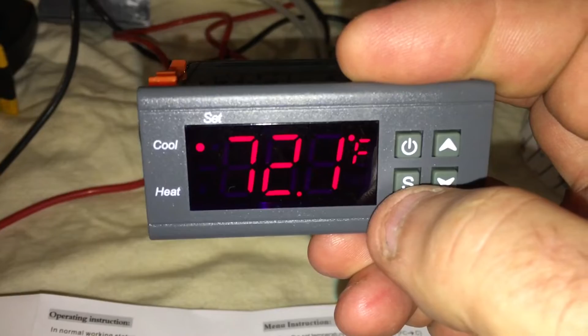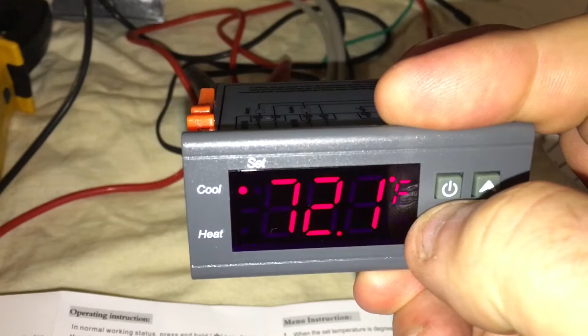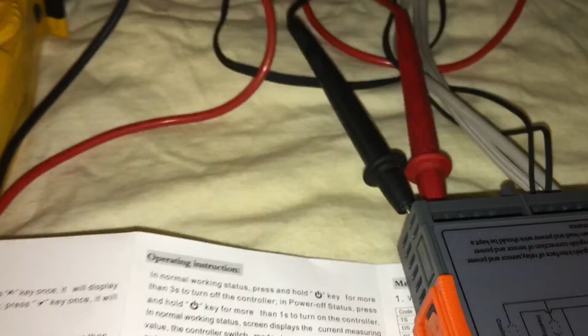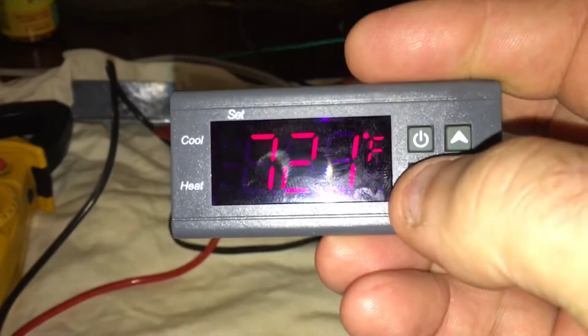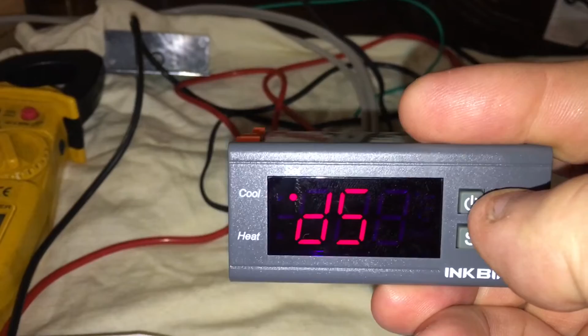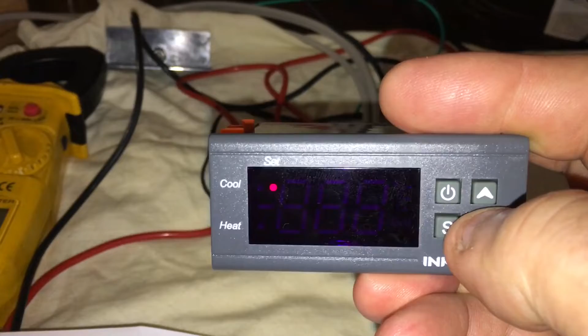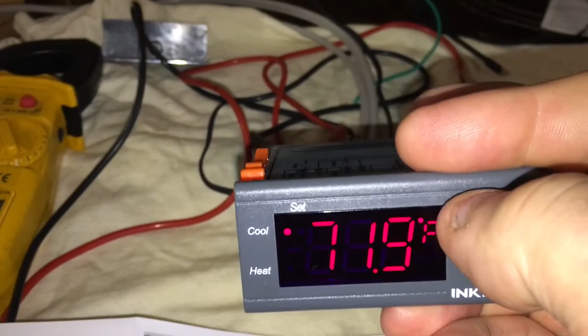Then your blinking is your 5 minute on the cool. See the blinking light? That's your compressor protection. So in 5 minutes that will go back to a solid light, and your relay will click. You'll tone out. So just hang on. Let me turn on the meter again. It always does a tone when you turn it on. We're blinking, that means we're in protection mode. So we hold the set button down for 3 seconds, go to your protection and go down to 0, and hit the power button, and you see it relay. She toned. You got it. Your relay kicked in, went solid on the red light on cool.